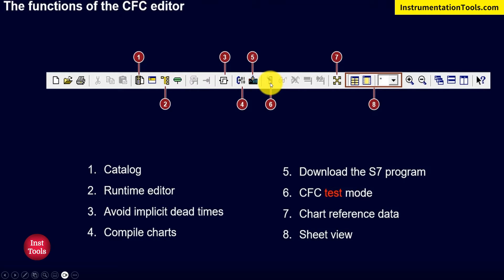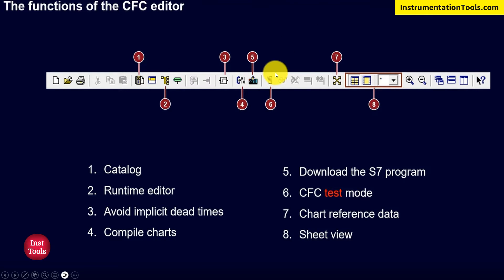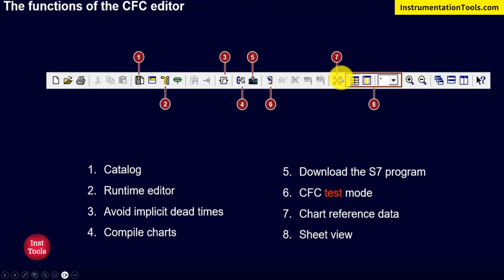The sixth icon is CFC Test Mode. This creates a virtual connection between our PLC and our CFC area, so after pressing it we can see the actual runtime data on our AS. The seventh is Chart Reference Data — all the data types used in the sheets for our CFC editor area can be seen in an Excel-like architecture where navigation is very easy.